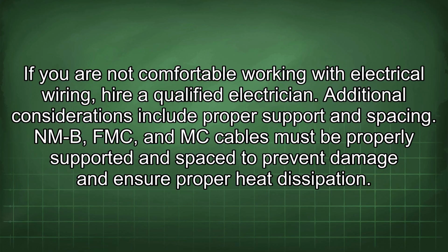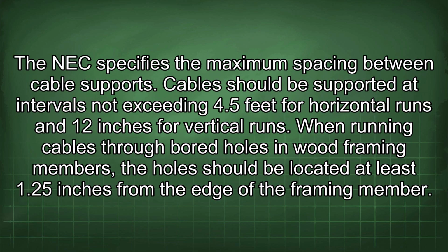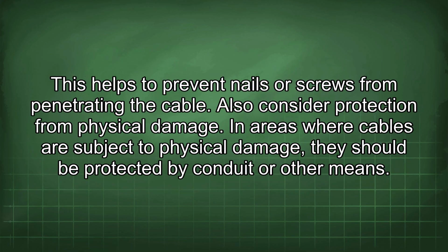Additional considerations include proper support and spacing. NM-B, FMC, and MC cables must be properly supported and spaced to prevent damage and ensure proper heat dissipation. The NEC specifies the maximum spacing between cable supports. Cables should be supported at intervals not exceeding 4.5 feet for horizontal runs and 12 inches for vertical runs. When running cables through bored holes in wood framing members, the holes should be located at least 1.25 inches from the edge of the framing member. This helps to prevent nails or screws from penetrating the cable.